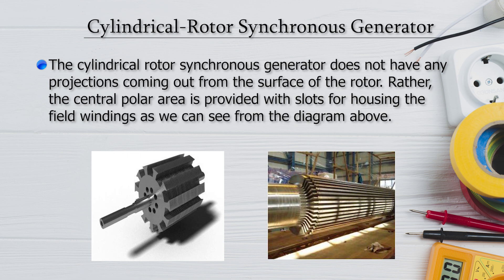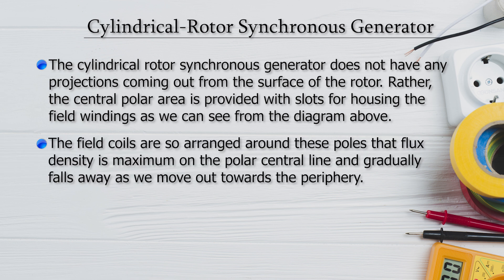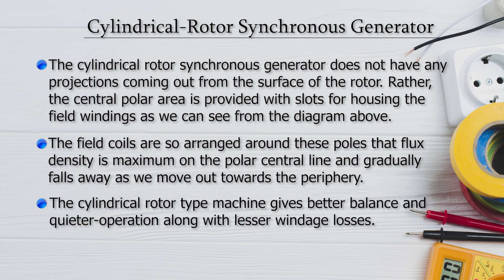The inter-polar area is provided with slots for housing the field windings. The field coils are arranged around the poles so that flux density is maximum on the polar central line and gradually falls away toward the periphery. The cylindrical rotor type machine gives better balance and quieter, noise-free operation with lesser windage losses. These windage losses are due to air friction — with a smooth surface and nothing projected out, wind resistance decreases and losses decrease.